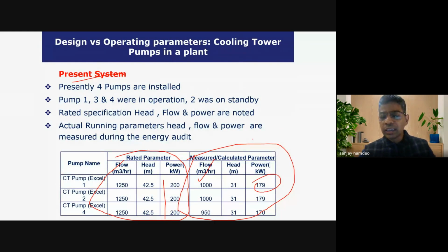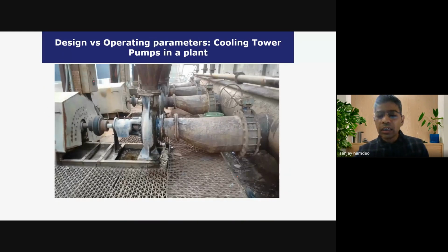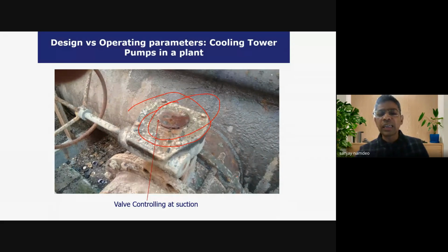So here you can see the design head is 4.2 kg or 42 meter, whereas the operating head is 3.1 kg only. So those who are from a mechanical engineering background can understand that this pump is highly over-designed by head. If the pump is highly over-designed by head, a higher head pump operating at lower head will deliver more flow and will consume more power. So in order to restrict that flow and the power, they throttle the valve. It means what is wrong? The pump is not correctly designed.